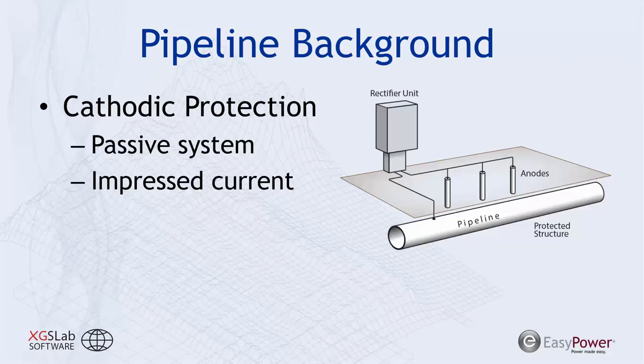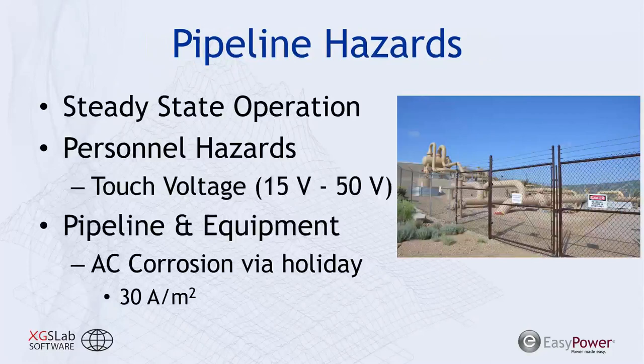Now, the types of hazards that we're concerned with from a transmission line to a pipeline from a steady state operation process is often a personnel hazard. You can have individuals making contact with an appurtenance and maybe unable to let go. Often an AC interference study looks at a limit of 15 to 50 volts depending on the pipeline owner and their operational practices. Another hazard is the pipeline's longevity itself.